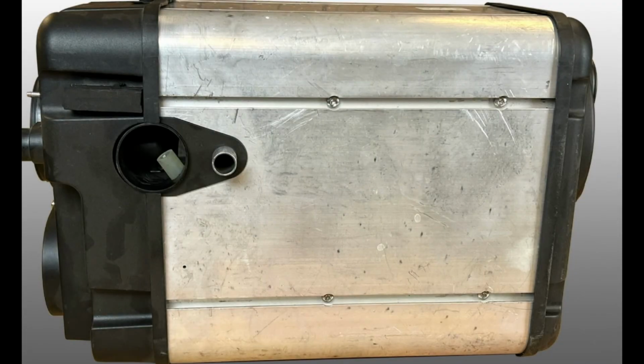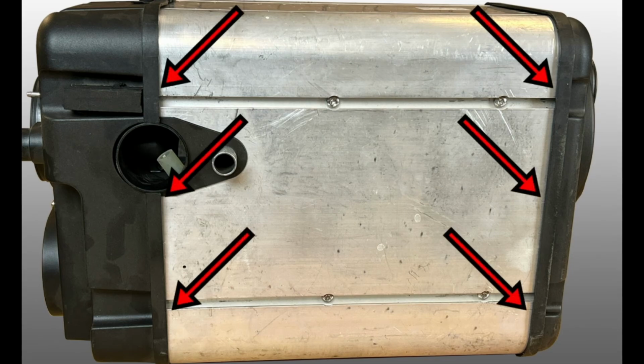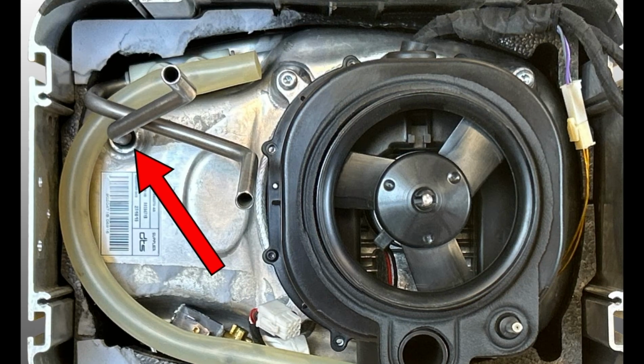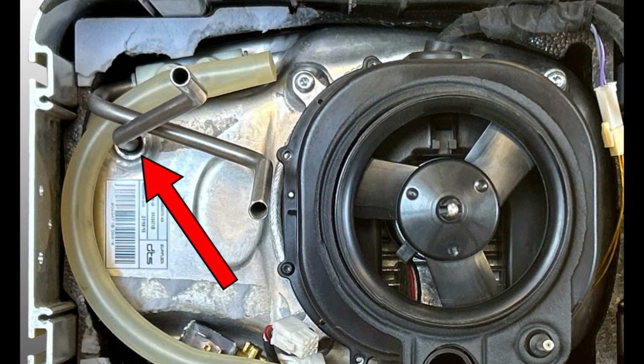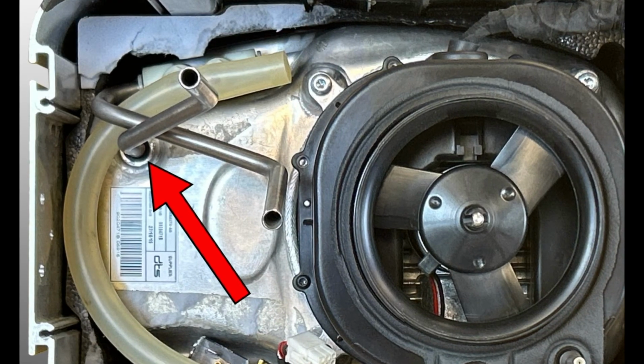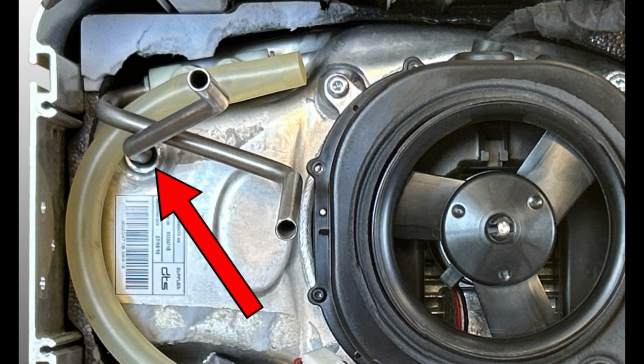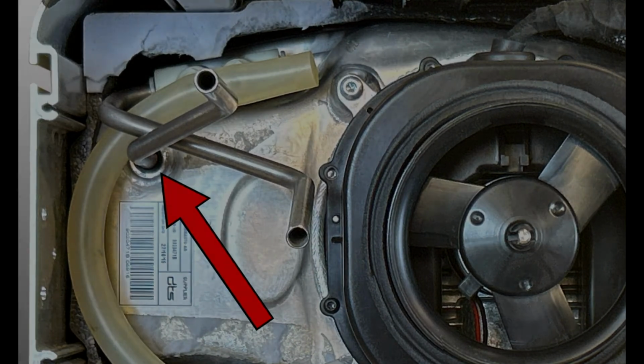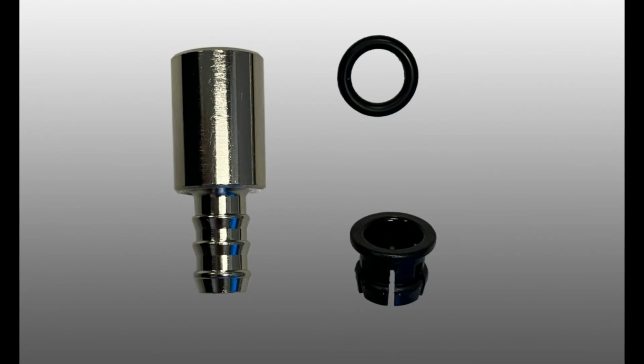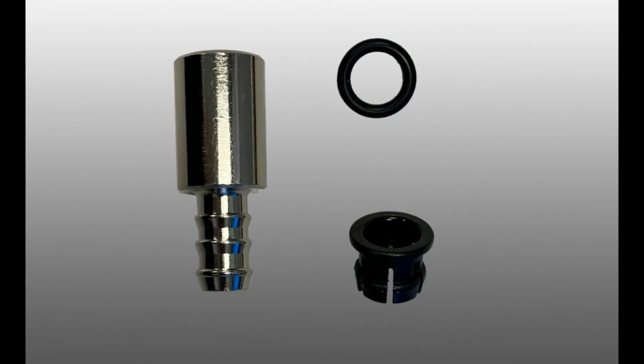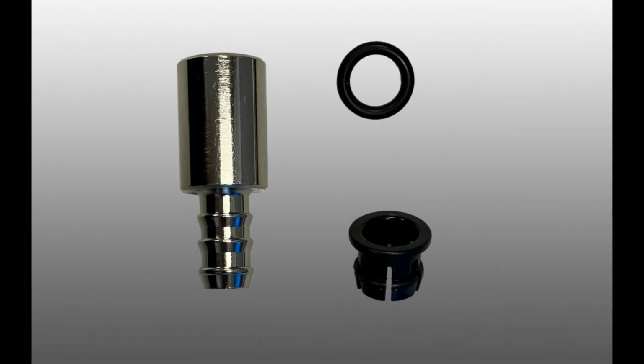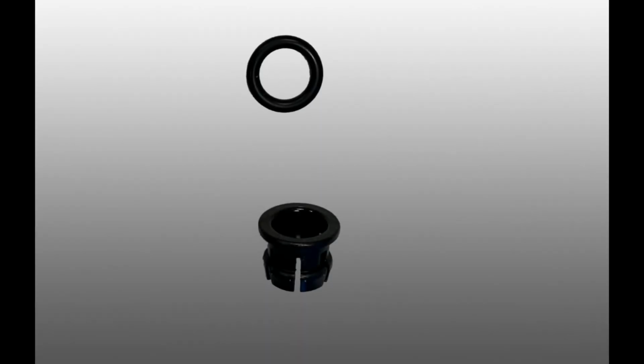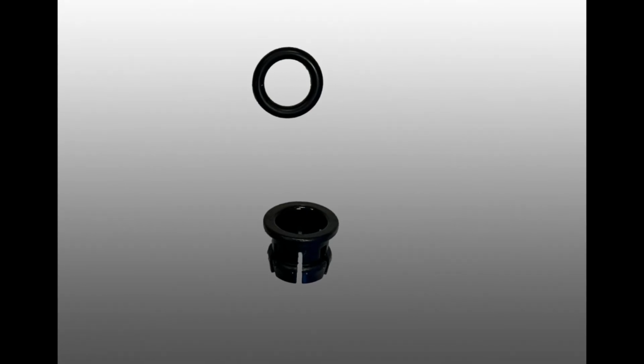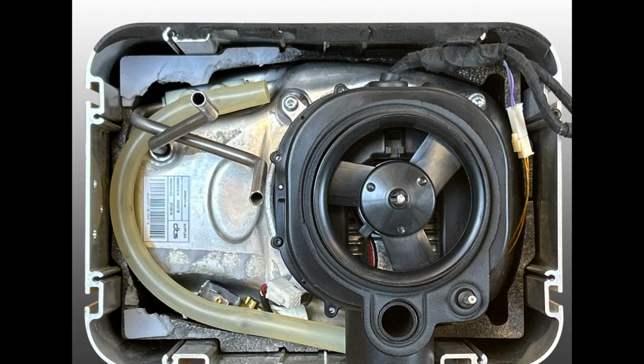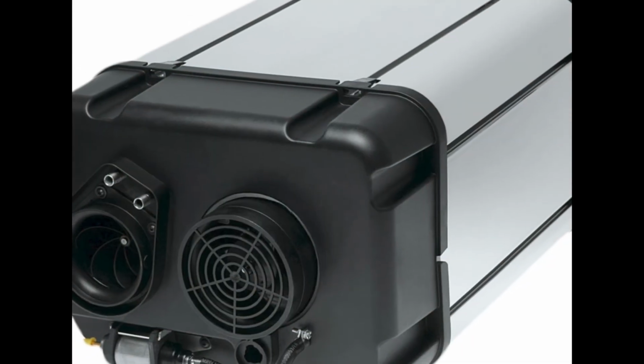If there is a leak at the boiler tank, you will find water escaping the case along the seams between the boiler housing and the two end caps. The first place to look is right here, where the water inlet pipe goes into the boiler tank. There is a rubber O-ring inside, and that can fail over time. After carefully removing the black collar, you will find the O-ring installed. A replacement O-ring can be sourced locally. If you need to replace the black collar, order a pair of brass barbed connectors available from the service parts list. Refer to that service parts list for the part number. Carefully remove the black collar from the connector and install it in the boiler tank, along with the O-ring. After replacing the parts, simply reassemble the heater and check to make sure that the leak has been fixed.